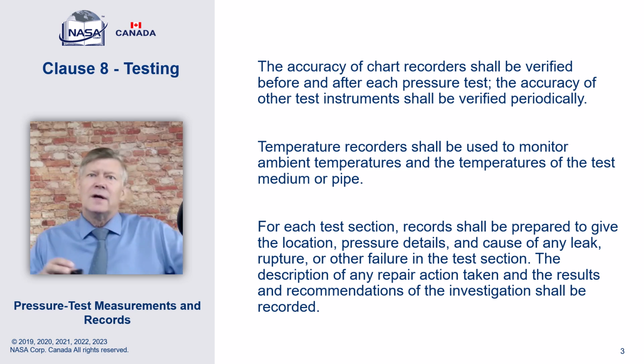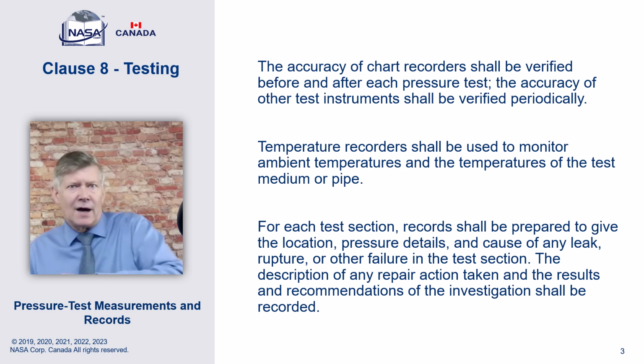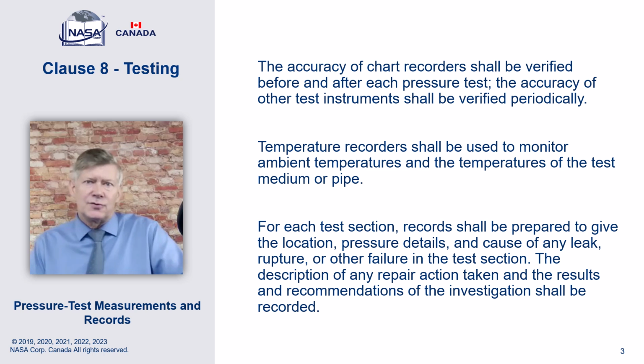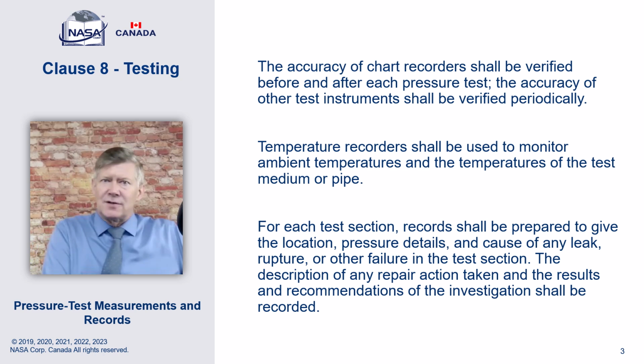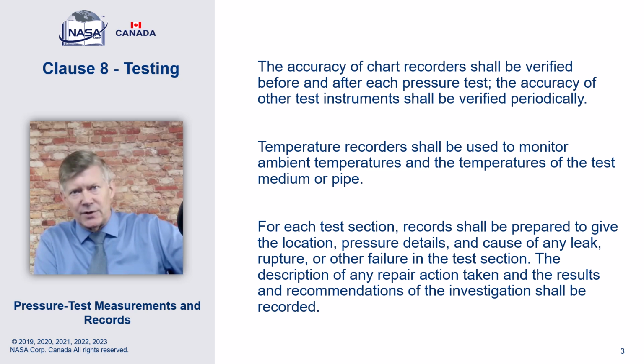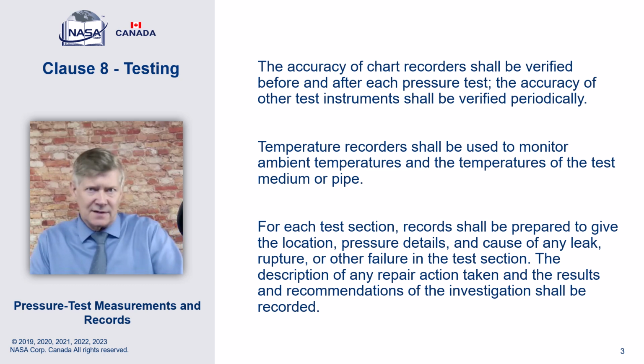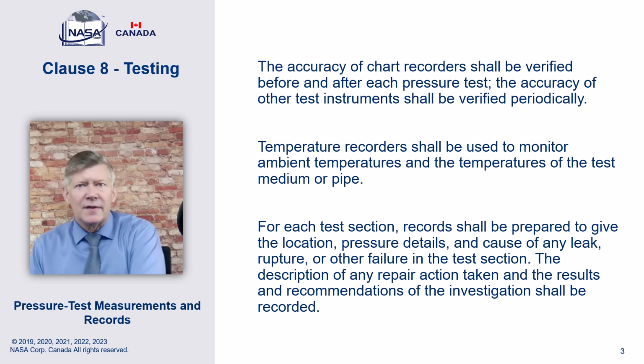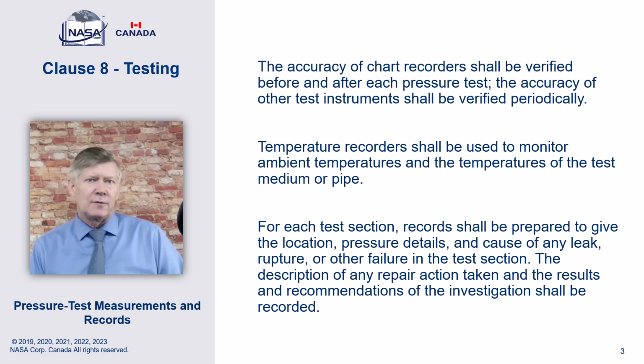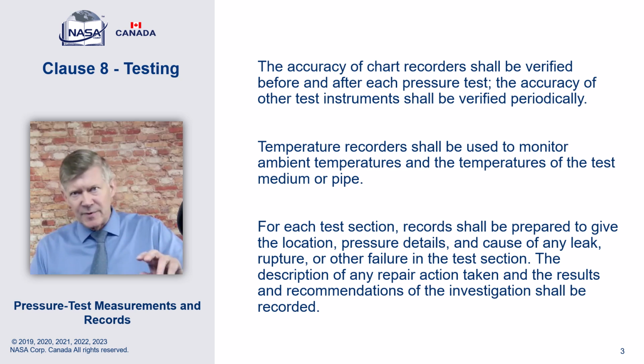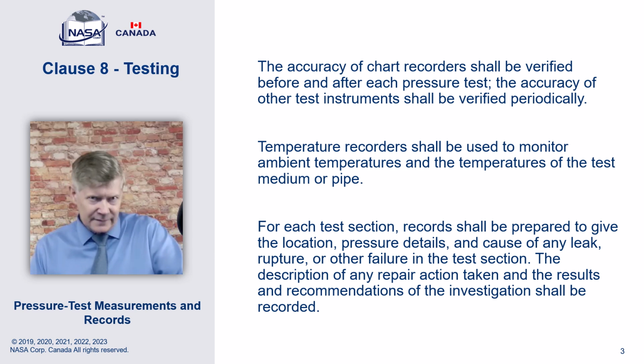Because again, these are for 24-hour, multiple hour tests, right? You don't want to do the whole test, everything's fine, go back to the shop and find out the recorder went out of calibration. Much better to run the 2 and have that indication there. The other instruments, again, it says verified. Again, we get to do it, but it says periodically. It even gives us the latitude of what that frequency is. Okay, it's just the primary recording instrument, the chart recorder, right, that needs to be verified before and after, or as accepted by industry, running multiples.